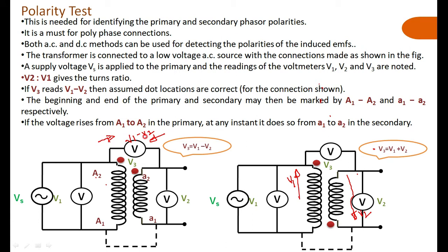There is addition between V1 and V2 — they are adding. Therefore, the polarity marks the highest potential of the primary winding at one terminal and the highest potential of the secondary at another terminal, because there is a rise in voltage in that direction. In that case the voltmeter reads V1 plus V2. Therefore you have to mark the dot at that point — that point has higher potential. You then mark the terminals as A1 and A2 accordingly.